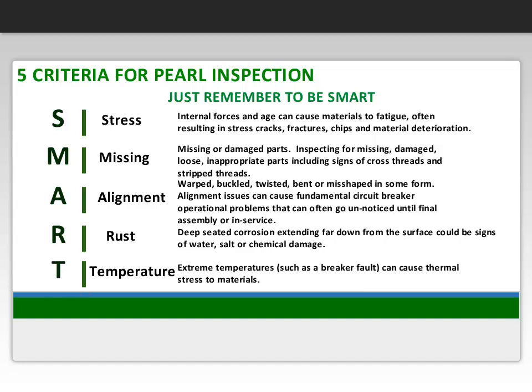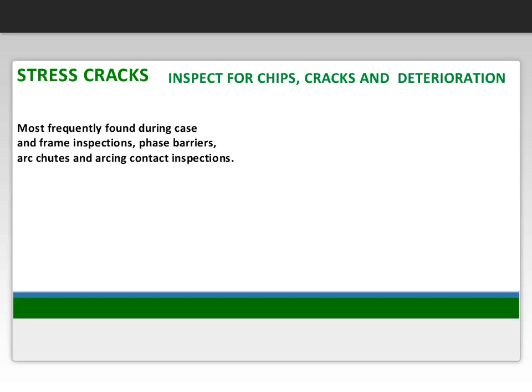Rounding out the acronym is T for temperature. Extreme temperatures, such as what you would see in a breaker fault, can cause thermal stress to the materials. We will go through some illustrations to further reinforce the concept. Inspect for chips, cracks, and deterioration. You will find this phrase repeated over and over in the inspection steps of the Pearl standard. Usually you will see it associated with pole bases, insulator phase barriers, and arc chutes.